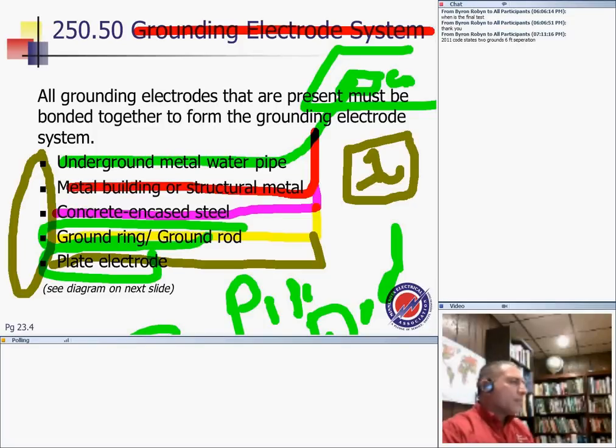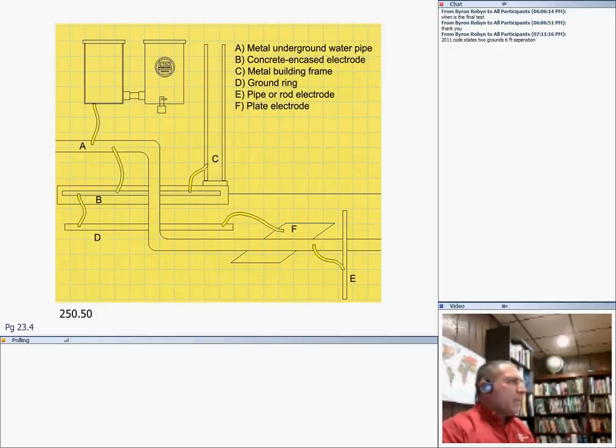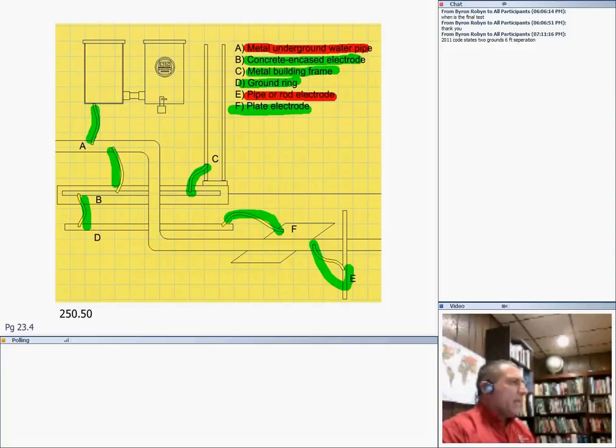Any questions, my friends? So the electrode grounding system, among other things: the underground water pipe needs supplement. The next one needs supplement, a pipe or a rod. These two need supplement. Everything else is a standalone big boy. This one is great. Ring is perfect. Plate is perfect. The only thing I need to supplement is the pipe or the rod. But if they exist in your building, guys, then you have to tie to all of them, as you can see. All of them have to be tied together if they exist in your building.